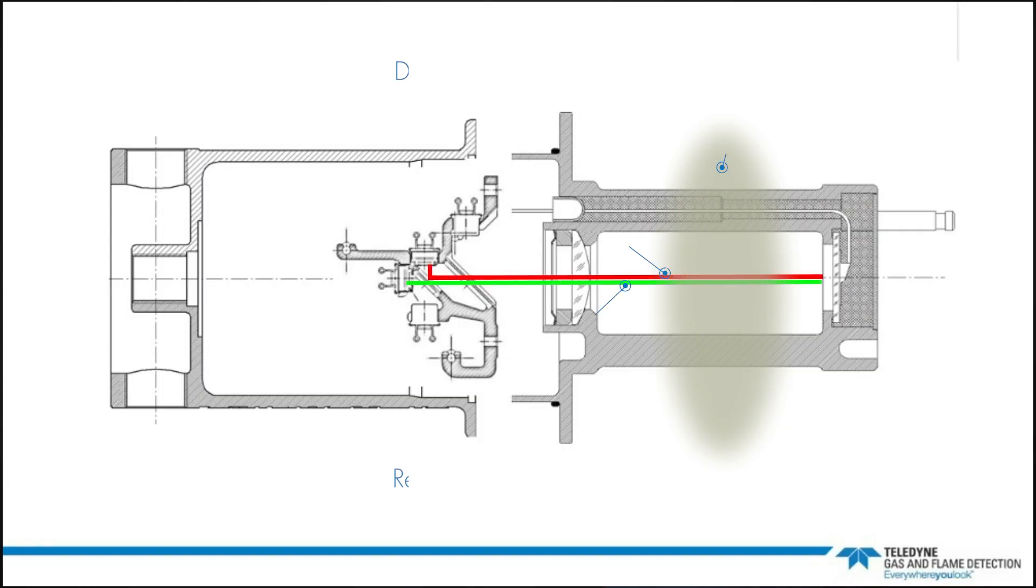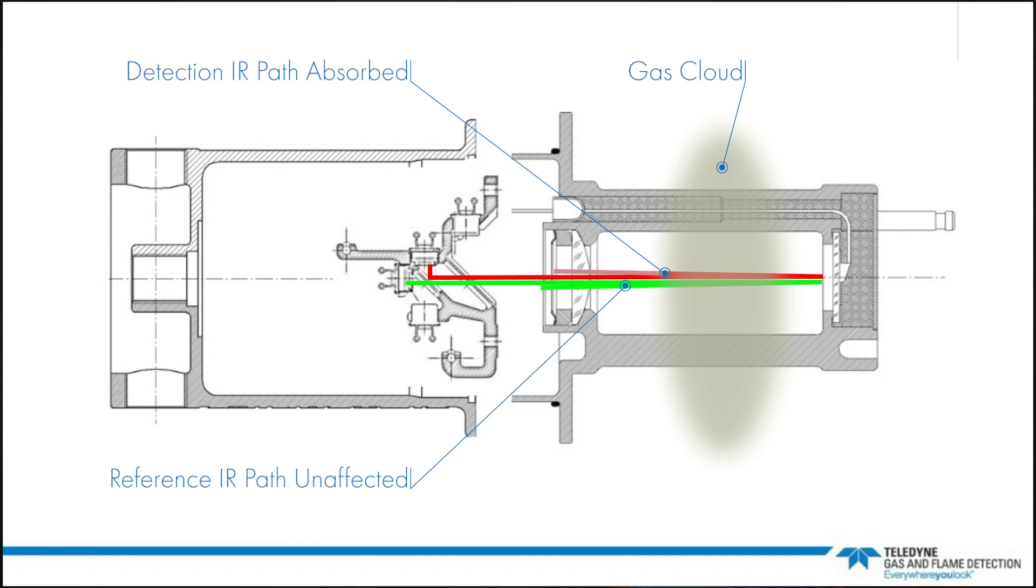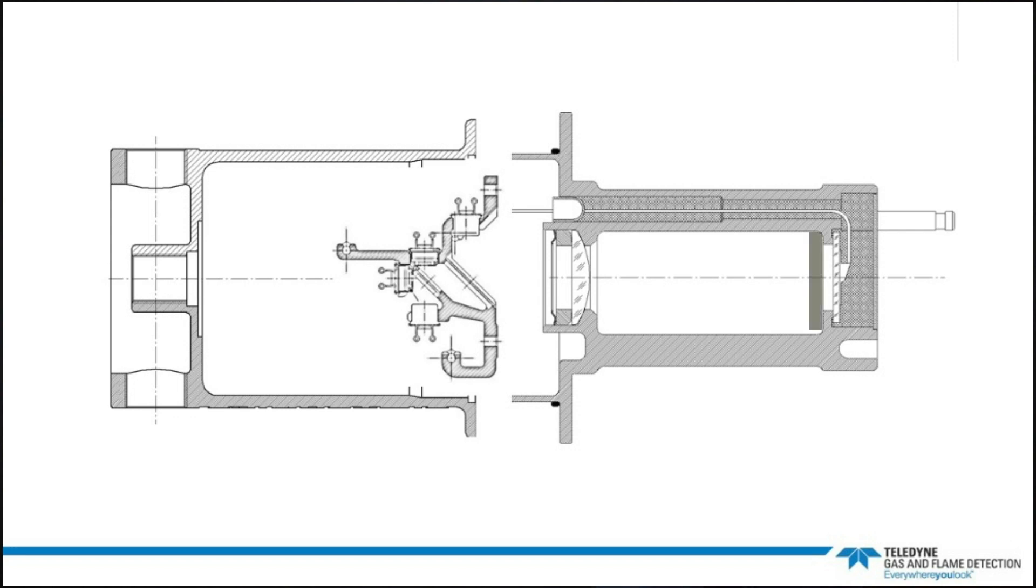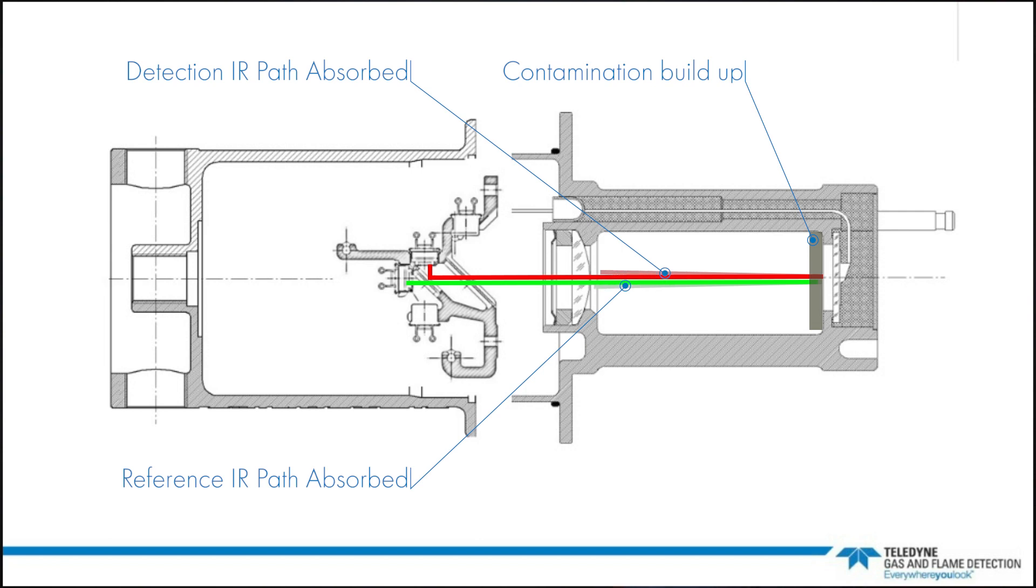Here you can see the gas present absorbing the detection path in the device and outputting as a gas event. Whereas here you see a contamination building up on the lens absorbing infrared in both the gas detection path and the reference path, telling the device there's a build up of contamination.